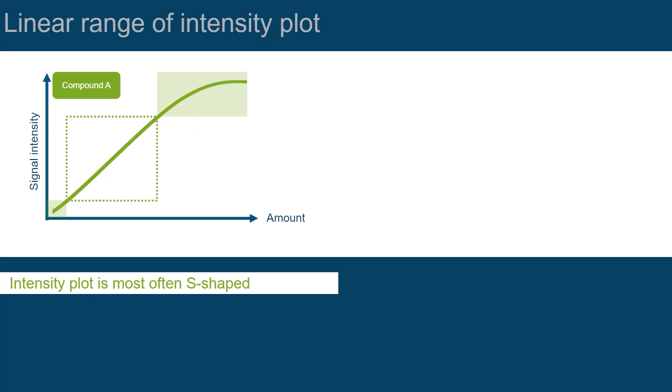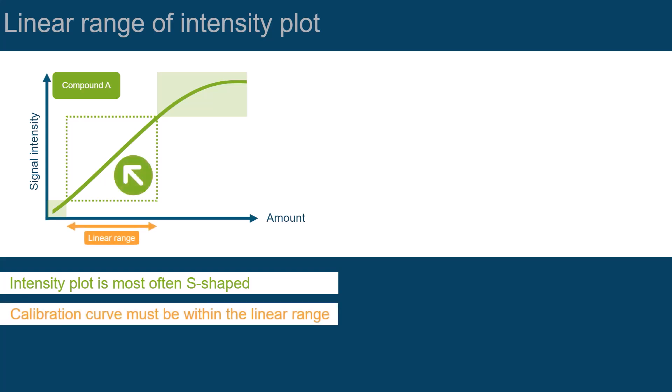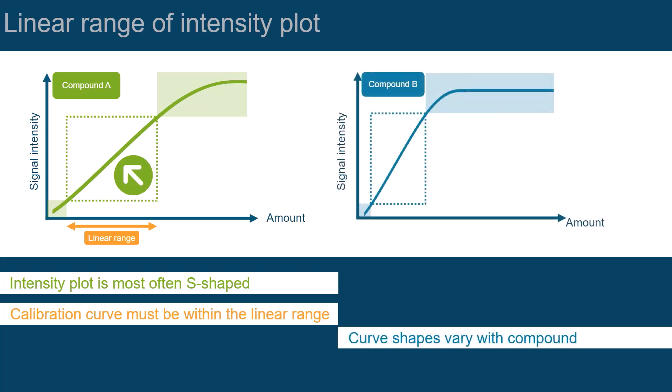Because we want to have a direct proportional change of the signal with the amount of the compound, it is mandatory that your calibration curve is within the linear range of the intensity plot. The curve shapes vary with the compound, and their linear range will therefore be different.